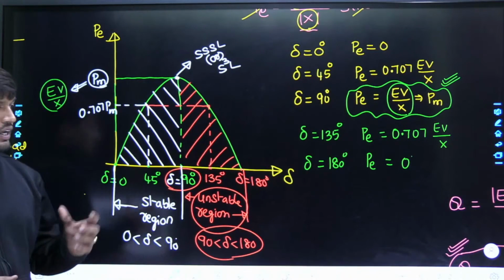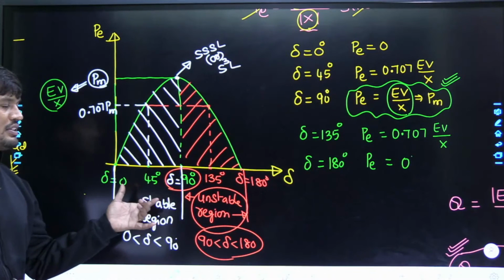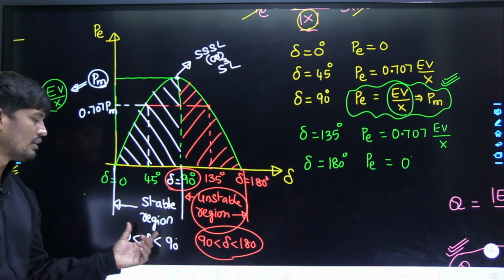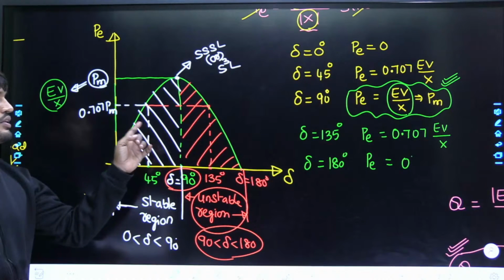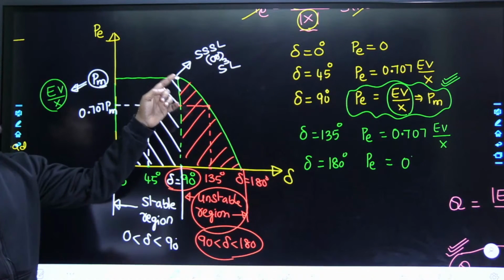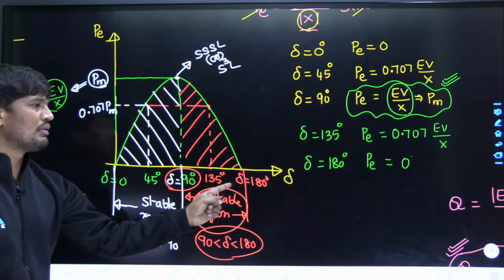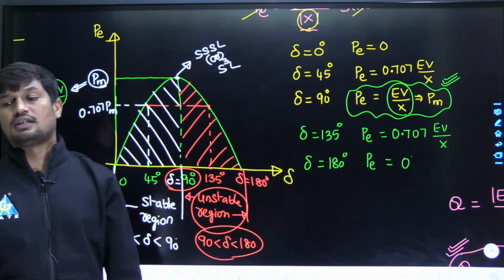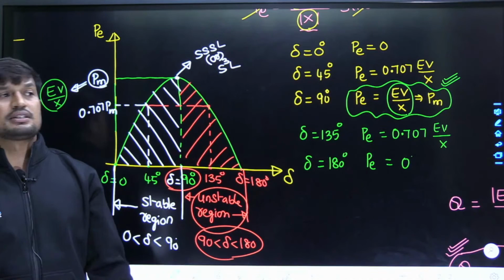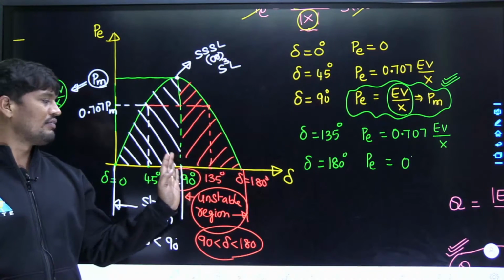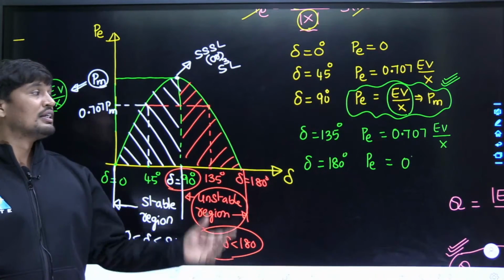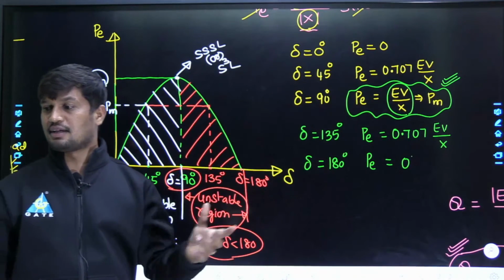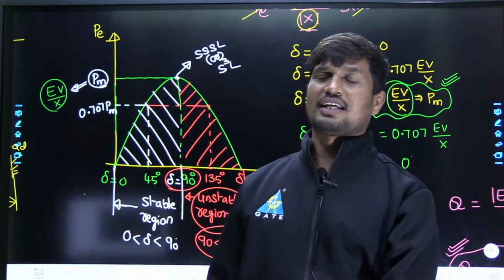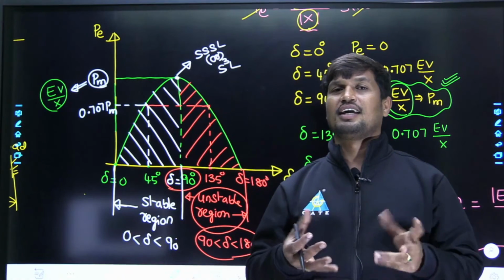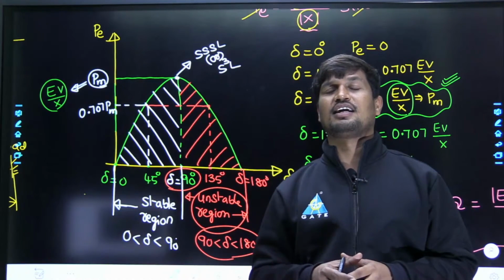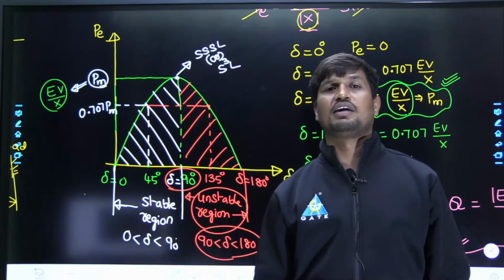That means, what exactly happens internally to the generator? When delta is between 0 and 90 degrees, the generator is more stable because it is generating more power and also transmitting maximum power. When delta increases beyond 90, the generator transmits less power to the load point, meaning the power delivered decreases as delta increases beyond 90 degrees. So something happens internally to the synchronous generator, involving its stator and rotor field winding, that we have to understand.